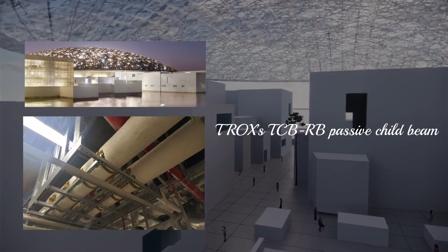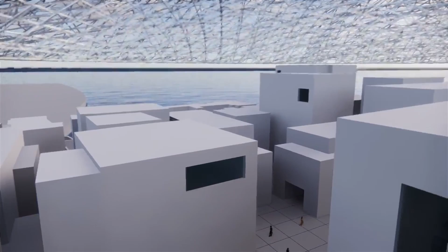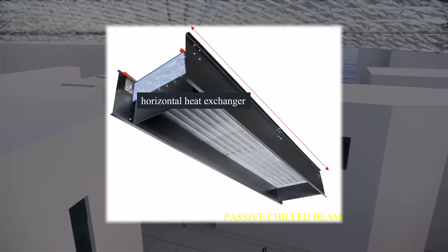The Trox TCB RB passive chilled beam was selected for important work, cooling a 24,000 square meter administrative building in the desert climate of the Arabian Peninsula. The passive chilled beam has a nominal length of up to 4,500 mm and a horizontal heat exchanger. Warm indoor air rises due to thermal buoyancy, is cooled by the heat exchanger, and then flows slowly back down into the zone.